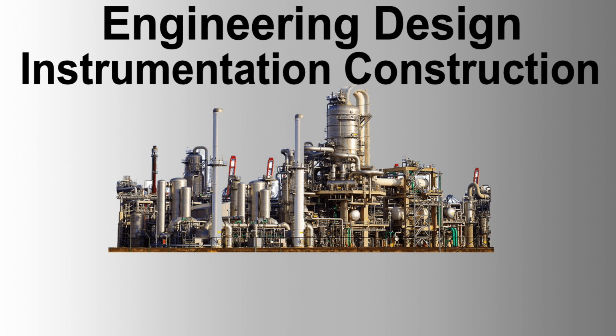Inspection. Regular inspections shall be conducted throughout the installation process to verify compliance with the project drawings, specifications, and standards. Inspections shall cover all aspects of the installation, including but not limited to material and equipment receipt and storage, installation of instruments, cabling, and supports, termination and connection of cables, tubing and piping installations, calibration and testing of instruments.